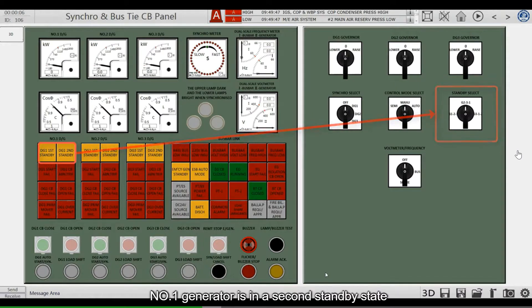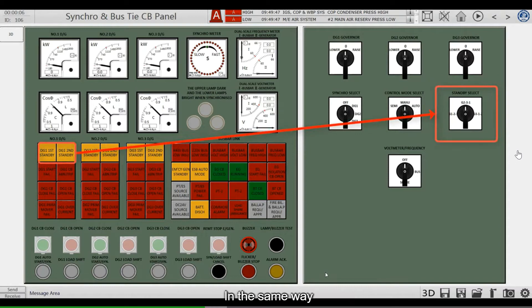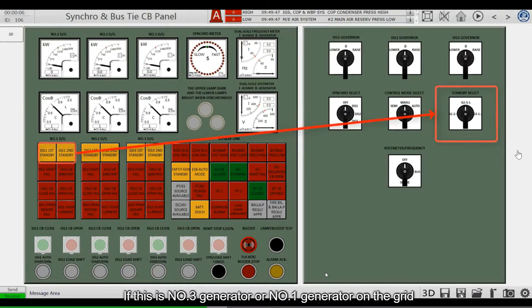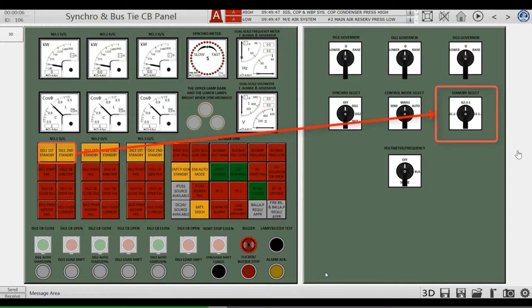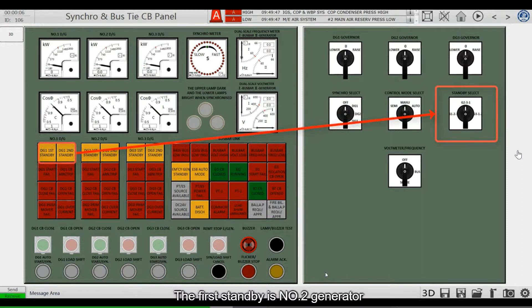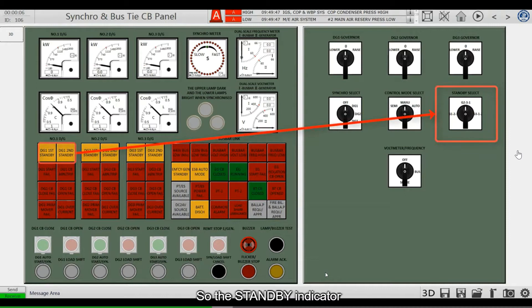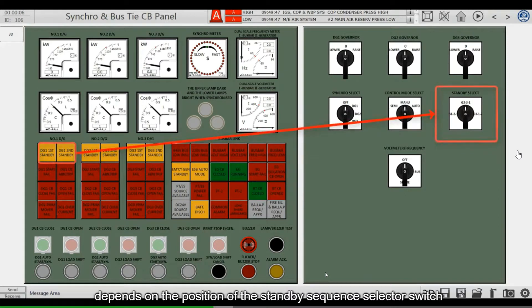Number 1 generator is in the second standby state. In the same way, if number 3 generator or number 1 generator is on the grid, the first standby is number 2 generator. So the standby indicator depends on the position of the standby sequence selector switch.